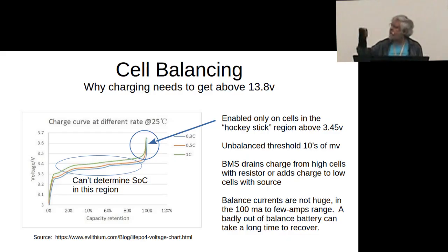Once you get it up into that region, hold it there, let the cells balance - the current will drop, and now you're absorbed and done, fully charged, everything's wonderful. At that point, if you want to drop it back down into that flatline region, float if you will, basically don't have any more current go into the battery. And if you want to use it like a UPS, you can drive your loads with a power supply, but only at 13.2, 13.3, somewhere in there. You can't go up to 13.8 - you can't use the float.